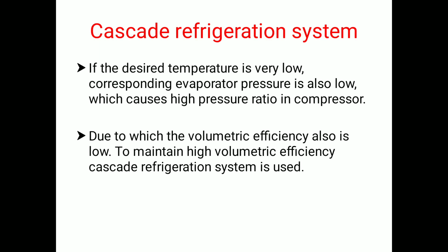If you observe, if the desired temperature is very low, then the corresponding evaporator pressure is also very low, which causes very high pressure ratios in compressors, due to which the volumetric efficiency is low. To maintain high volumetric efficiency, a cascade refrigeration system is used.